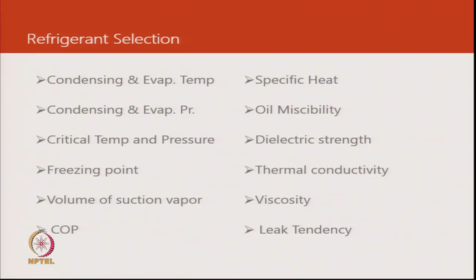Dielectric strength. So, you might wonder why oil miscibility, why dielectric strength. Oil miscibility is to allow for oil to circulate with the refrigerant. The compressor requires oil for lubrication, and that oil will flow with the refrigerant. If it is miscible, it will return back easily, and the compressor will continue to work reliably. Then dielectric strength is because of hermetically sealed compressors. Since we have electrical windings that are exposed to the refrigerant, a high dielectric strength means there is low probability of short circuiting.